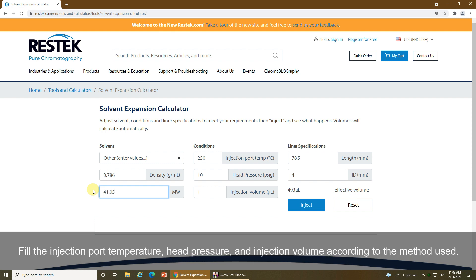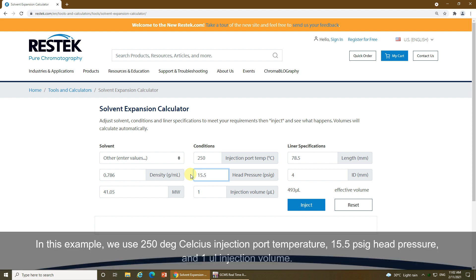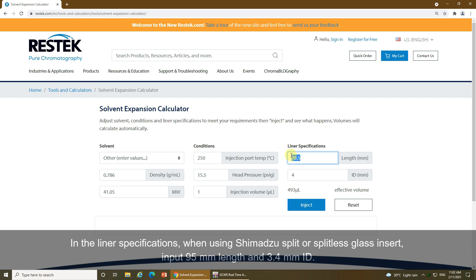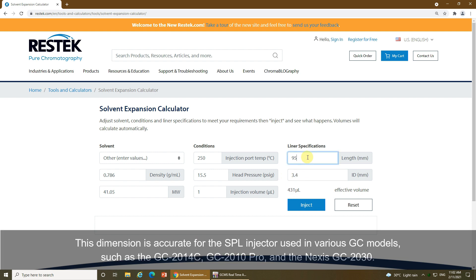Fill in the injection port temperature, head pressure, and injection volume according to the method used. In this example, we use 250°C injection port temperature, 15.5 PSIG head pressure, and 1 microliter injection volume. In the liner specifications, when using Shimadzu split or splitless glass insert, input 95 mm length and 3.4 mm ID. This dimension is accurate for the SPL injector used in various GC models such as the GC2014C, GC2010 Pro, and the Nexis GC2030.